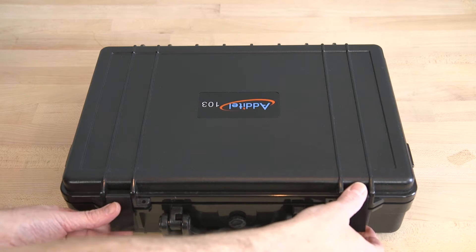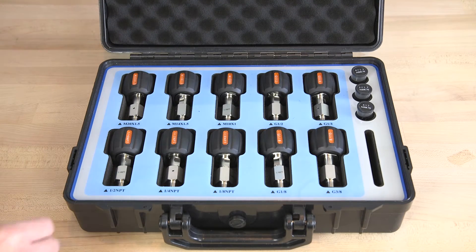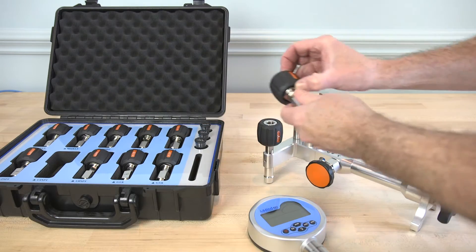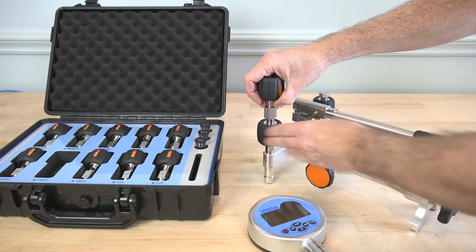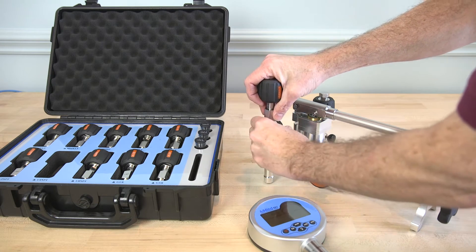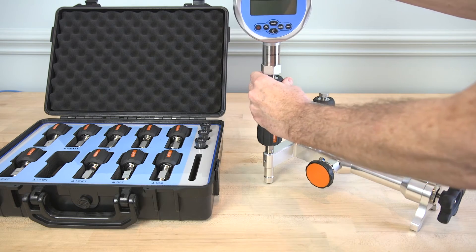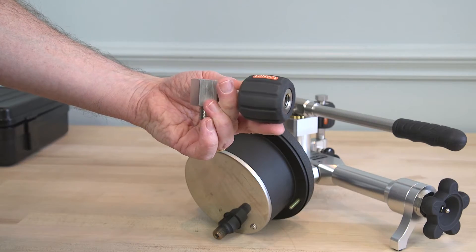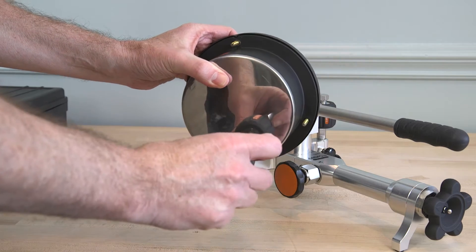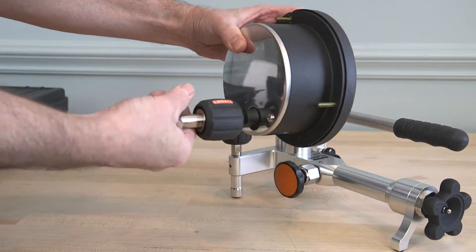The 103 series of adapters are hand-tight quick connectors that eliminate the need for Teflon tape or sealants. These adapters screw directly into the Additel pumps or manifolds, and then the test device with NPT, BSP, or metric threads can be installed on the adapter with no tools or sealants. A right-angle quick connector allows pressure gauges with back-mount fittings to be tested in the proper orientation. All 103 series adapters can be used to 15,000 PSI.